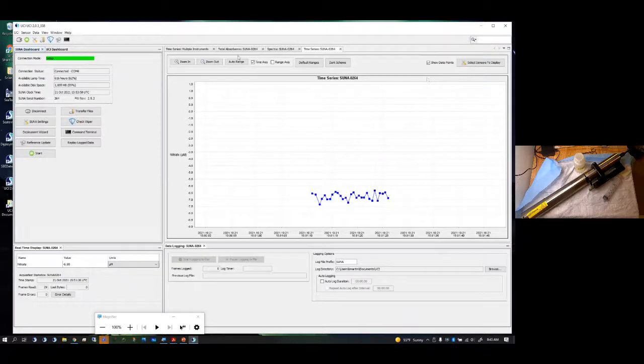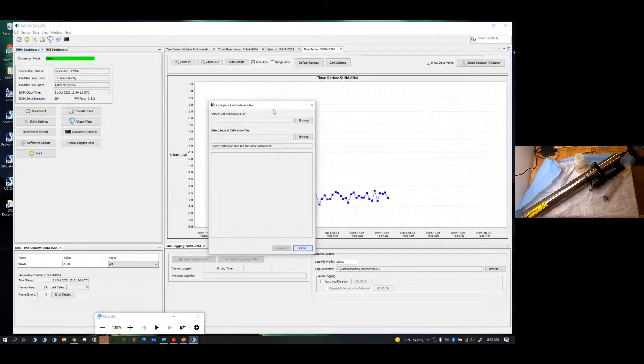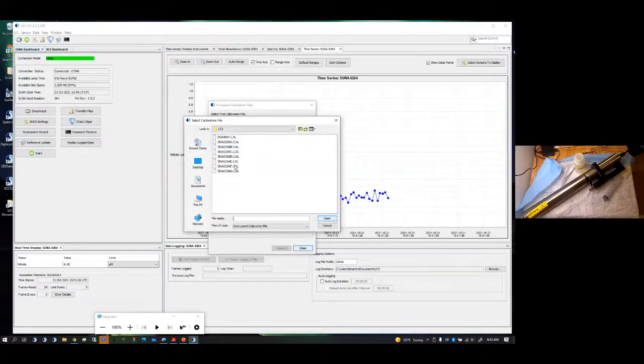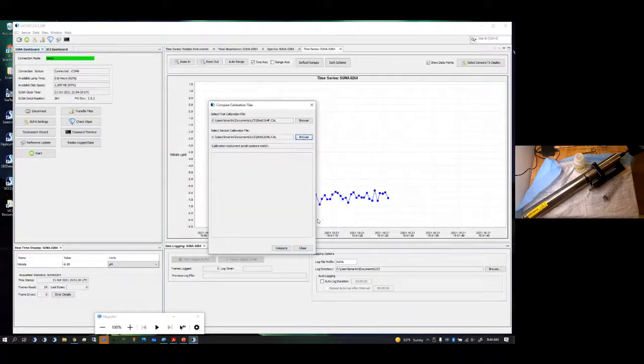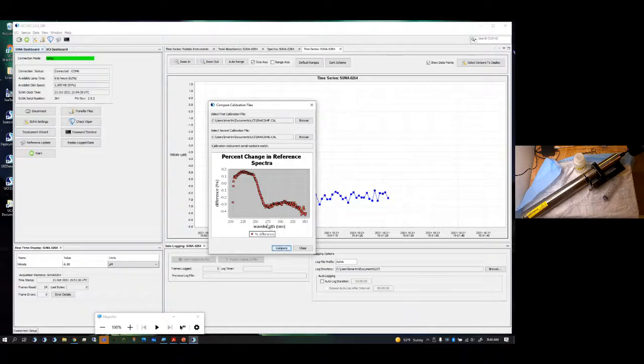One thing you can do as well that I do like to do sometimes is you can look at the SUNA and you can compare your calibration, all right? So here, if you want to see how your calibration files have changed, you can select your first one. So I will select F. Oh, I'm sorry. This is actually looking at calibrations that I've downloaded onto my computer. So we're not going to look at the most recent one, but I can look at two in the past. And then I'm going to do my second calibration file, G. And then I'm going to compare. All right. And you can see that that's a percent change in the reference spectra. So that was from the other two previous ones, and that's pretty close. That's typically what you'll see.